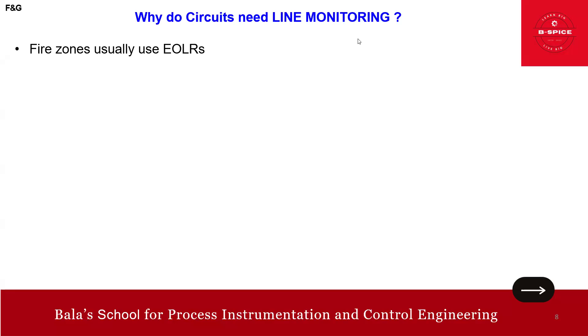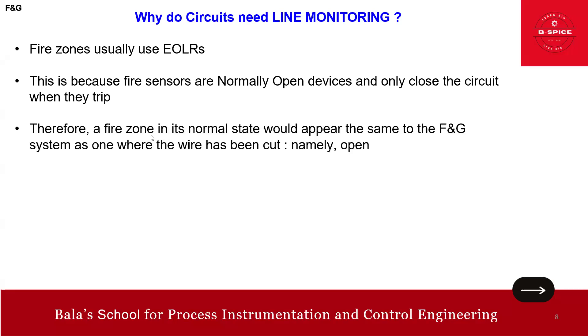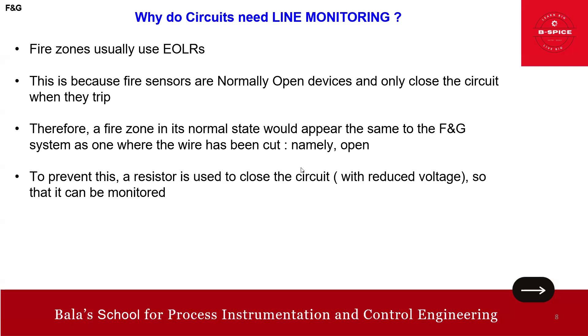Fire zones usually use the end-of-line resistor system because fire sensors are normally open devices — they only close the circuit when they trip. Therefore, a fire zone in its normal state would appear the same to the fire and gas system as one where the wire has been cut — both look like an open circuit. To address this, the resistor is used to close the circuit with a reduced voltage so that it can be monitored.